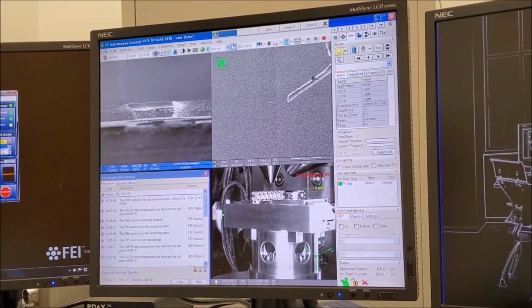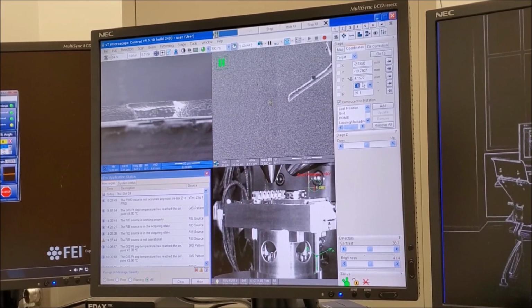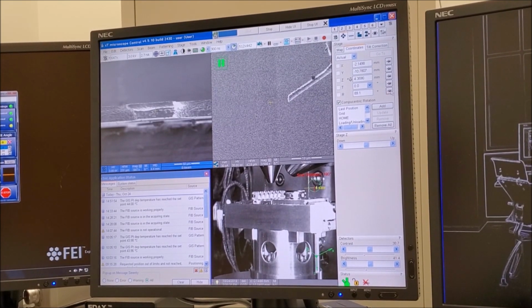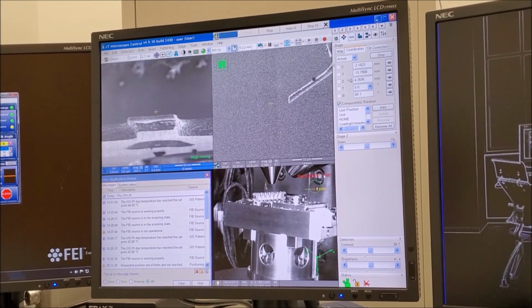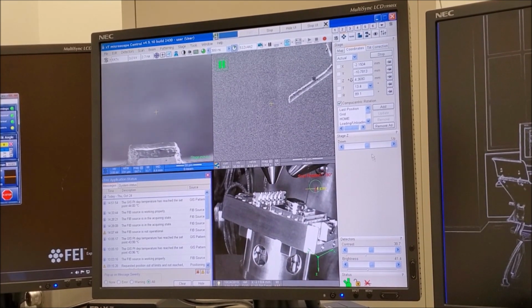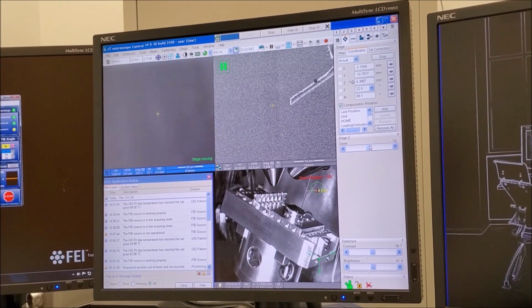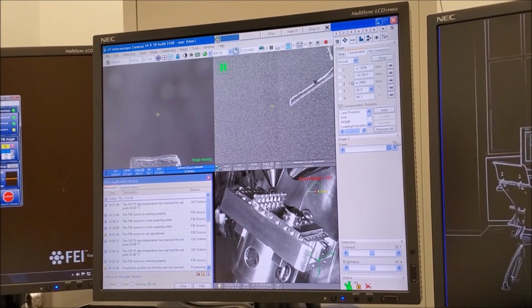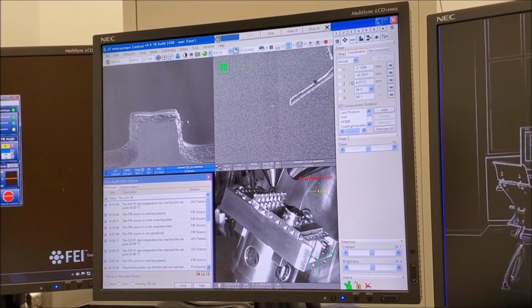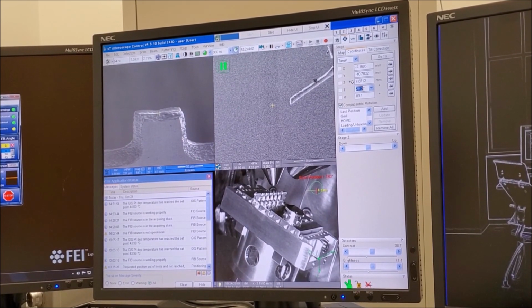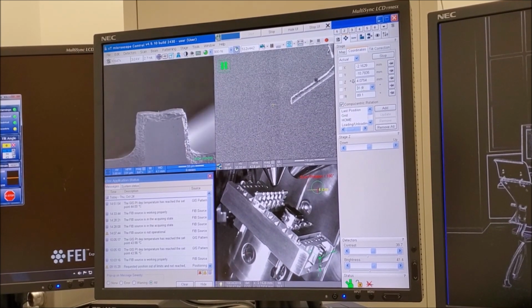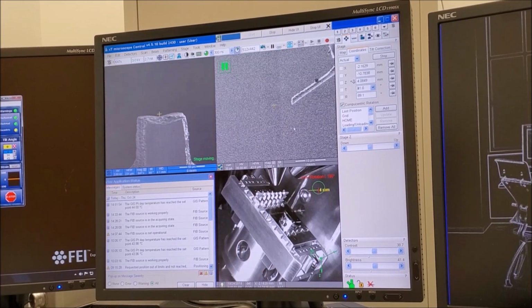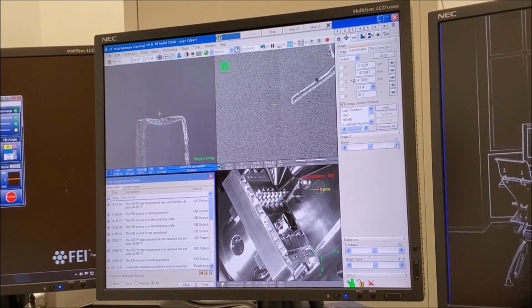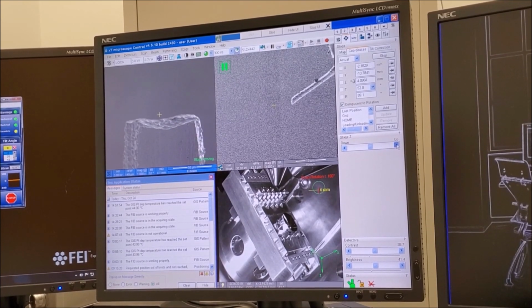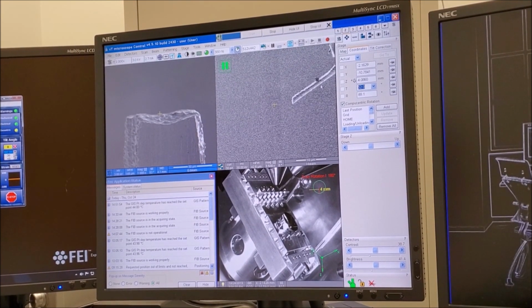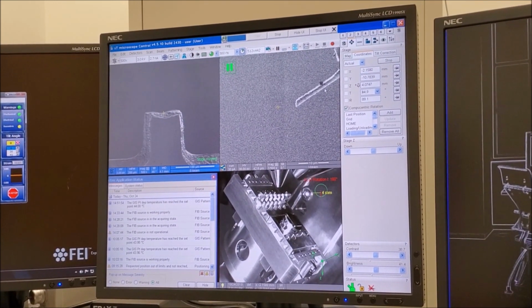Then enter the navigation module and set the stage tilt to 26 degrees. If the grid moves from the center of the image after the stage is tilted, adjust the stage Z control to return the grid to the center of the image. Then change the tilt to 52 degrees, and again, if the grid deviates from the center of the image, adjust using the stage Z control. With the grid post now at eucentric height, return the stage tilt to 0.